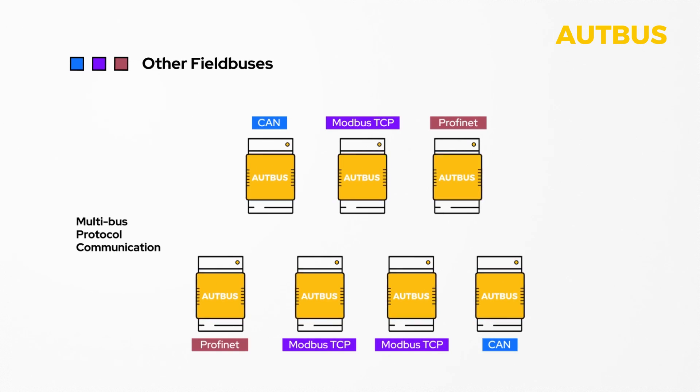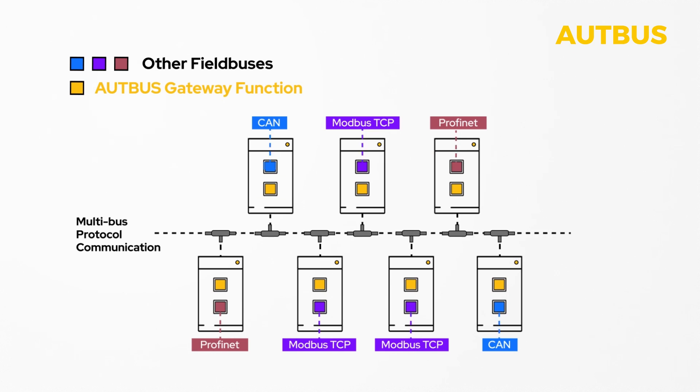Another key advantage of AUTBUS is that it offers multi-bus protocol communication of different fieldbus protocols by means of the AUTBUS gateway function. It enables integration into devices without protocol transformation by tunneling the data from one AUTBUS node to another. It is even possible to transmit different fieldbus protocols at the same time via the same AUTBUS network.